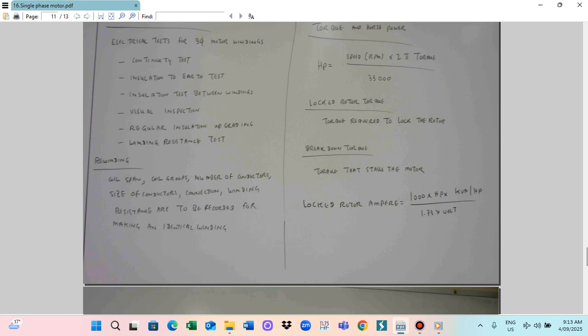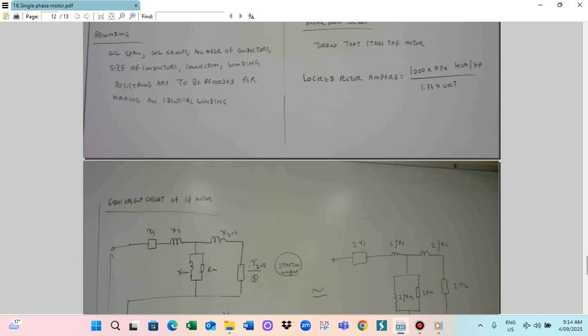Motor maintenance. Electrical tests for the 3-phase winding have to be done: the continuity test, the insulation test between the windings, visual inspection, regular insulation upgrading, and winding resistance tests are important for motor maintenance. For rewinding, the coil span, coil groups, number of conductors, size of the conductor, and connection of the windings are to be recorded for making an identical winding.